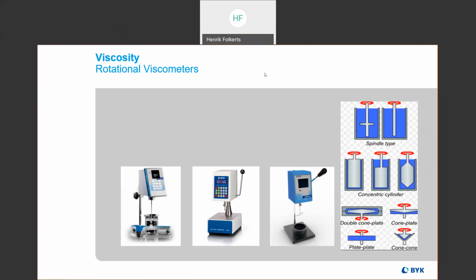viscosity in centipoise. Whereas before with those cups, it's measuring the kinematic viscosity in centistokes, and that has to do not just with the viscosity of the liquid, but also with the density of the liquid. So with the cups, the density of the liquid comes into play when measuring viscosity. The rotational viscometers are independent of the density, and so the unit is in centipoise rather than centistokes.